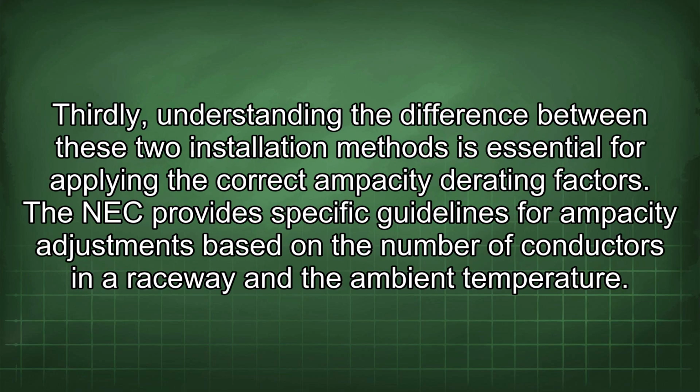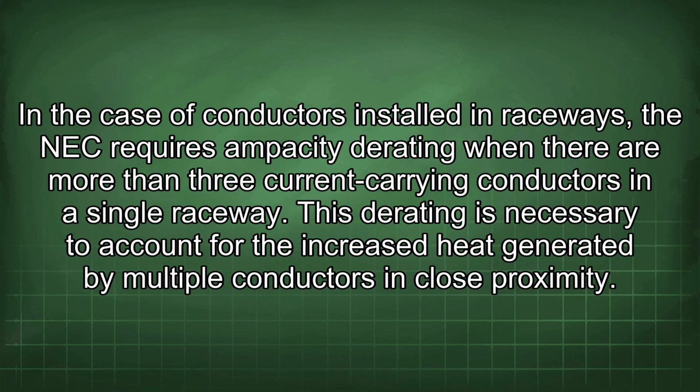Thirdly, understanding the difference between these two installation methods is essential for applying the correct ampacity derating factors. The NEC provides specific guidelines for ampacity adjustments based on the number of conductors in a raceway and the ambient temperature. In the case of conductors installed in raceways, the NEC requires ampacity adjustment when there are more than 3 current-carrying conductors in a single raceway.